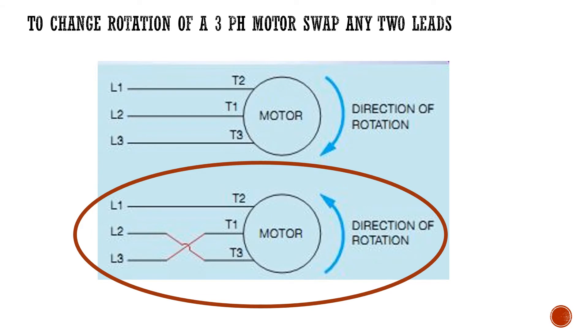So remember, to change the rotation of a three-phase compressor motor or blower motor, swap any two leads.